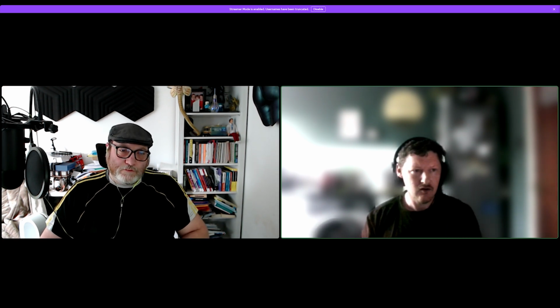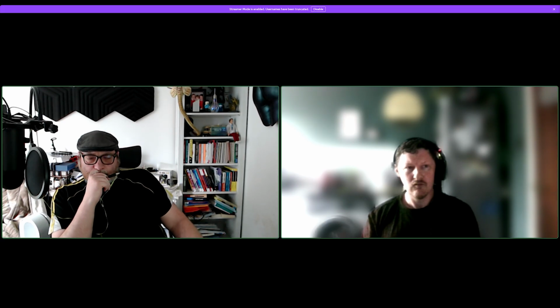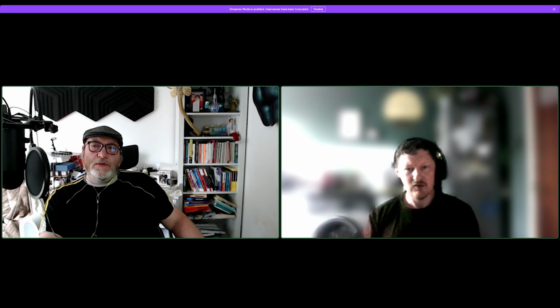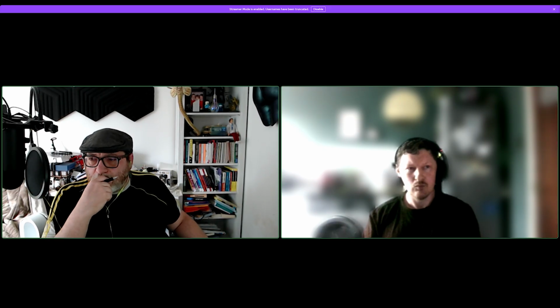So it led to a chat with one of the members of Discord, trying to discover on his testing a sort of level. So 1 would be okay, but he would say it was an FI. And then if it was like 2 to 5, he'd say, well, I want it to be a C3, an improvement required. So it led to this: what do you code? Do you code at all? Is it a problem? I said that, yes, you're singly testing a conductor, but 643.3.2 says about it being the main switch and the final circuits connected together, so you have the 1 over RT calculation.